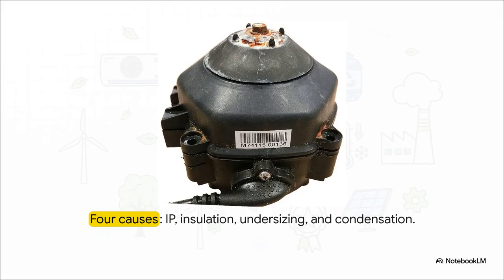And man, you can really see what happens when those specs fall short. Just look at the visceral rust and corrosion on that motor housing. There's no way around it. The data points to 4 main root causes here. First up, inadequate IP protection. When motors are exposed to water spray without proper sealing, moisture gets right in, and boom, internal corrosion.